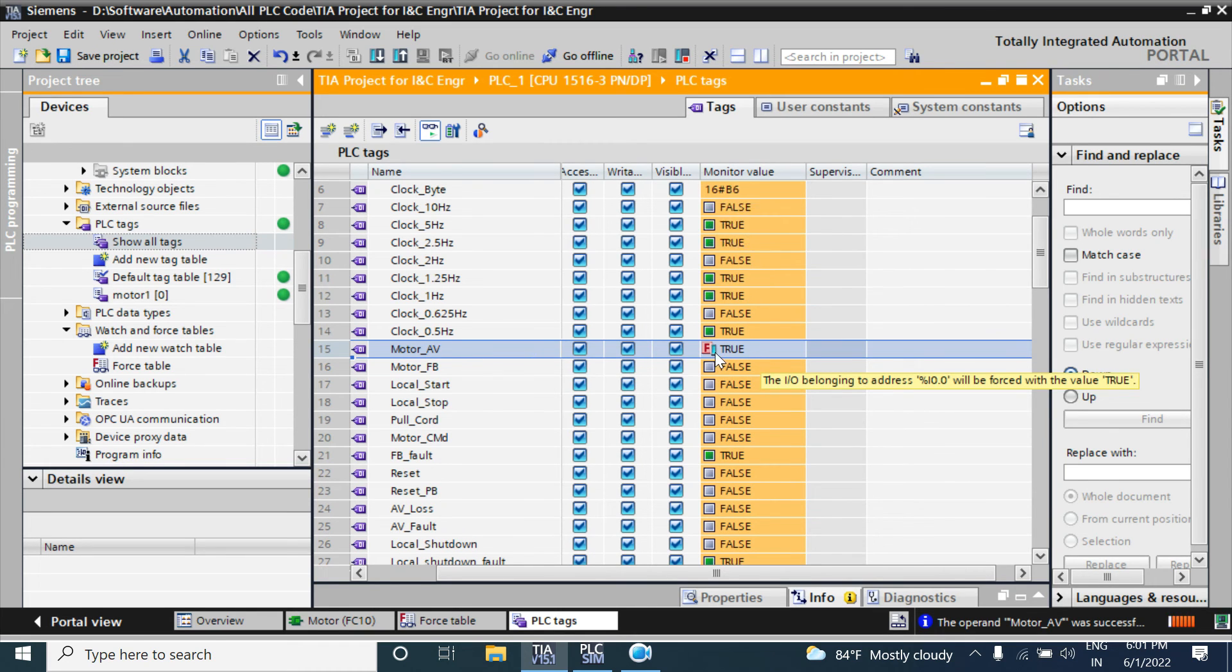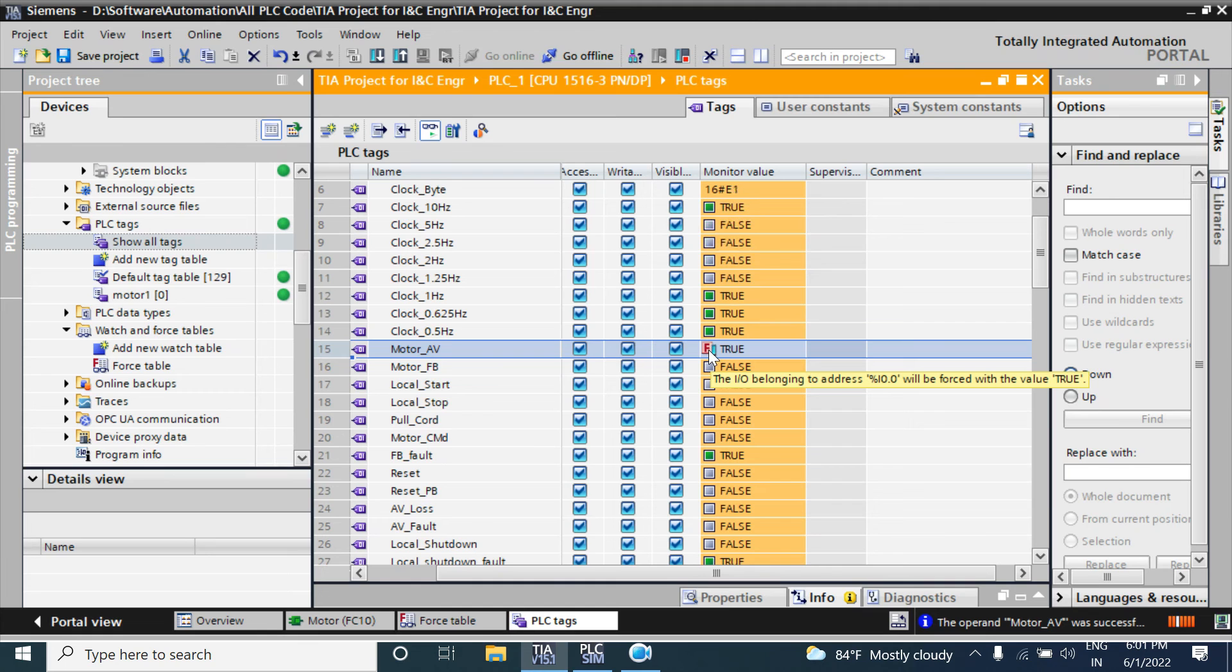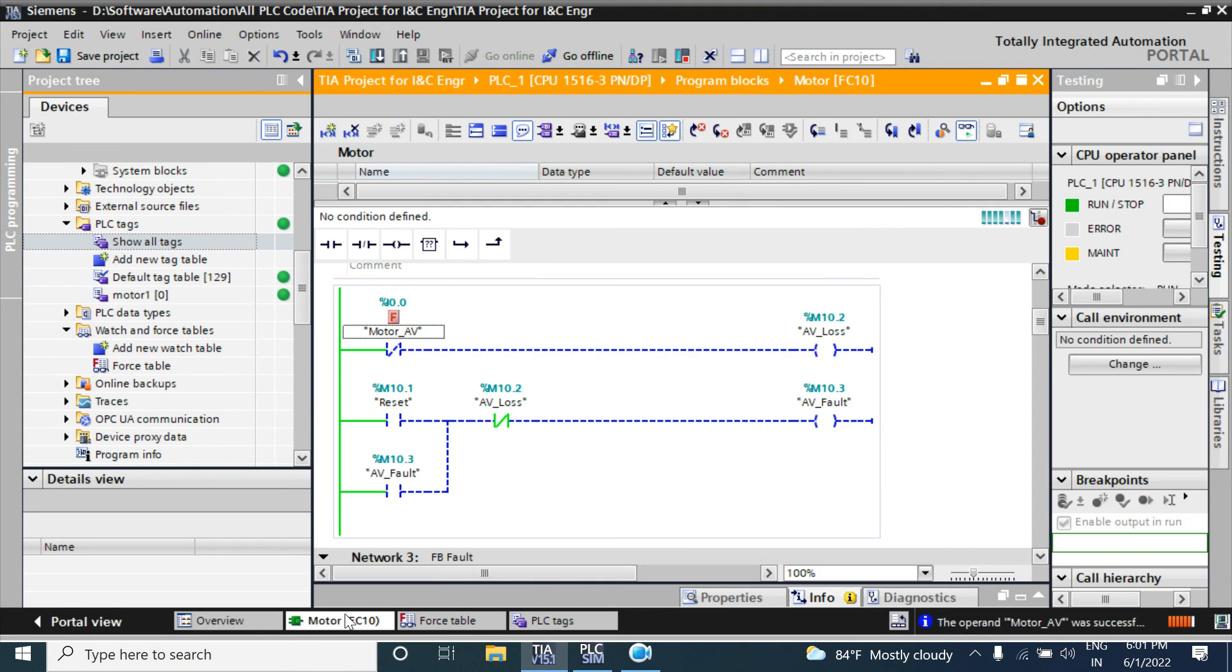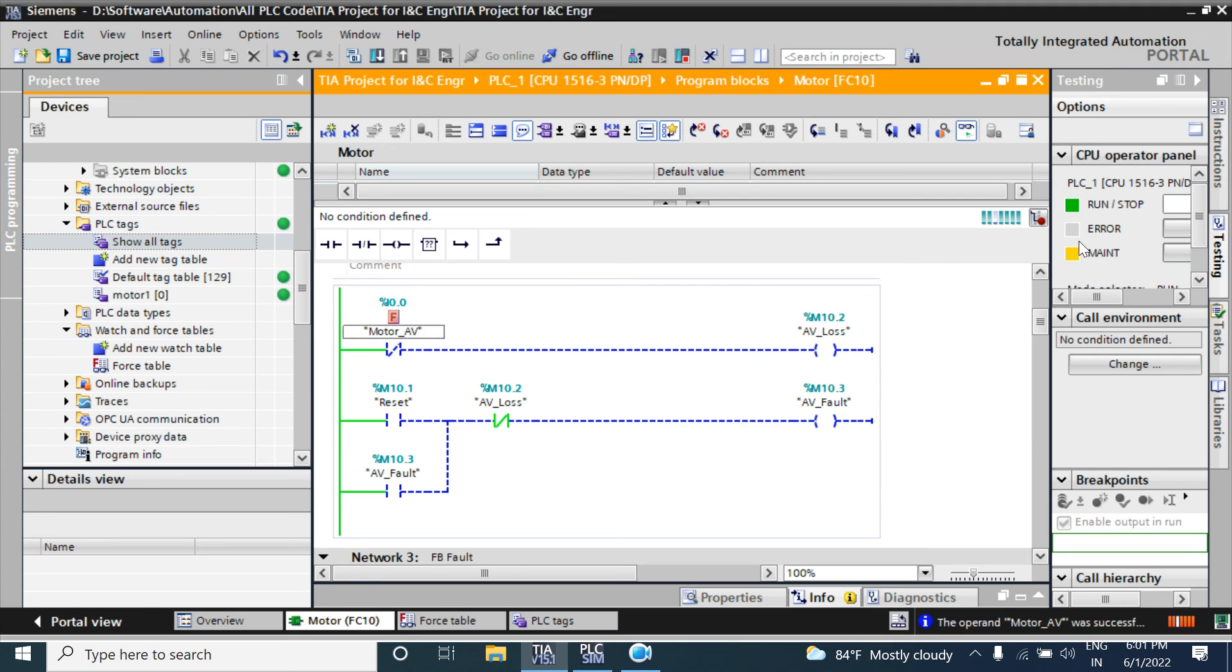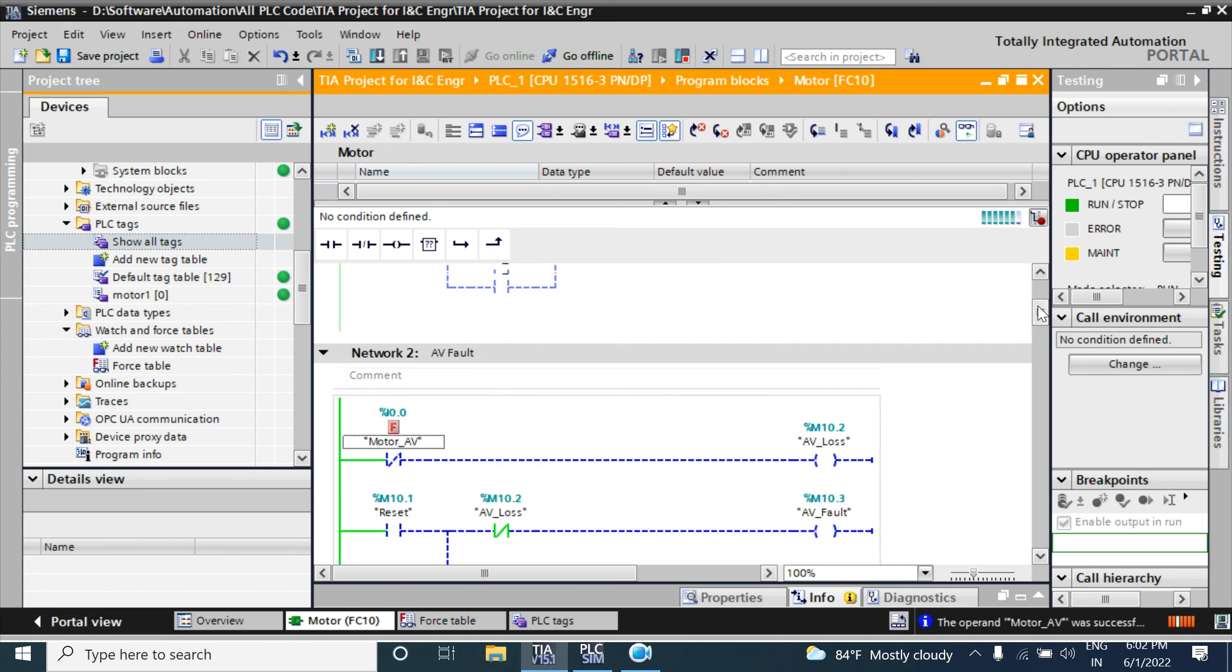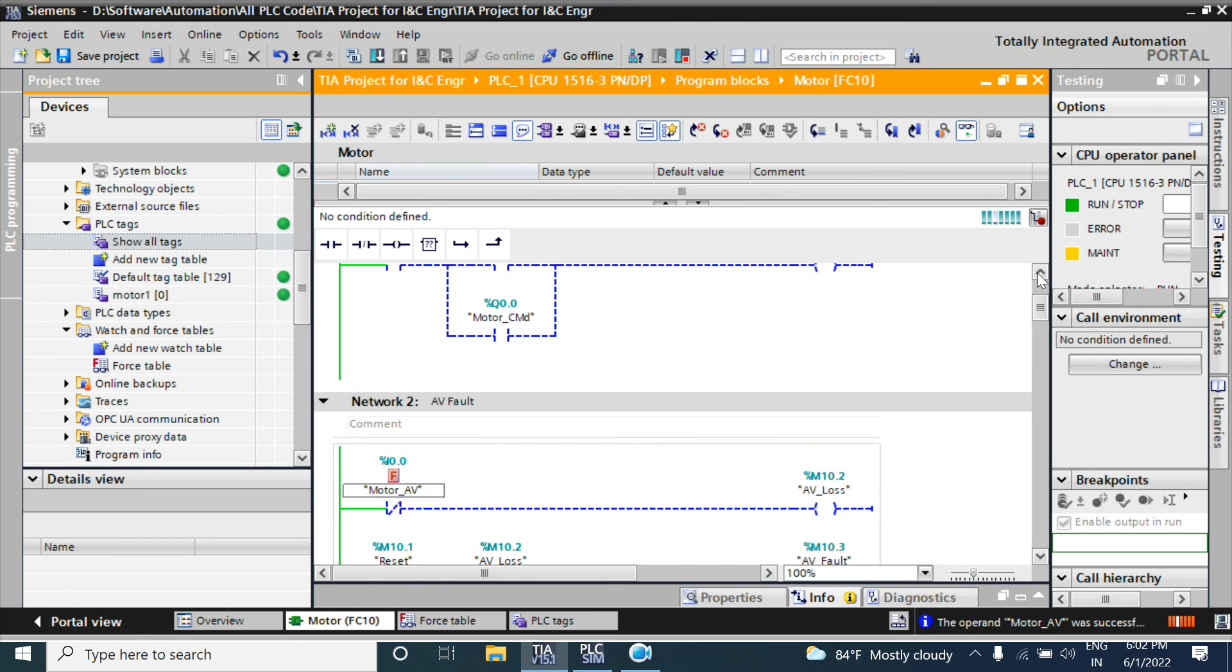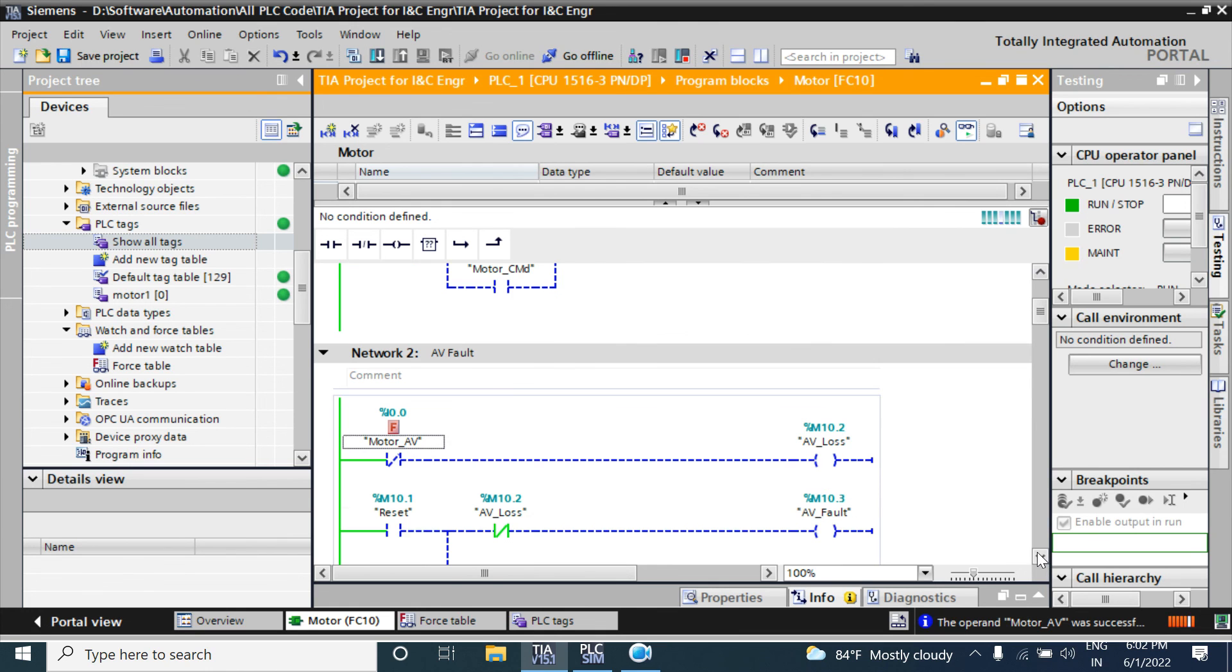If any I/O is forced, it will show a letter F red mark. Also, in your physical PLC, the maintenance LED will glow yellow. You can also see this in the virtual simulation PLC simulator - the maintenance LED will glow.